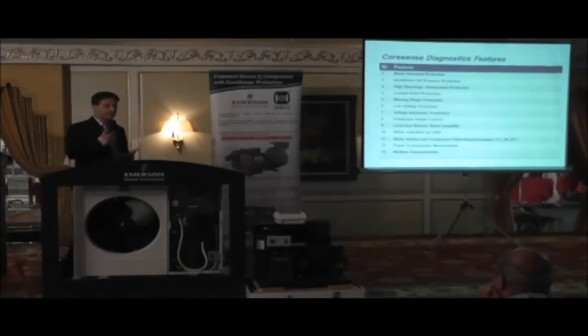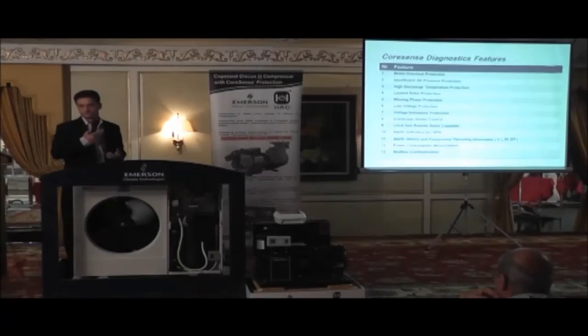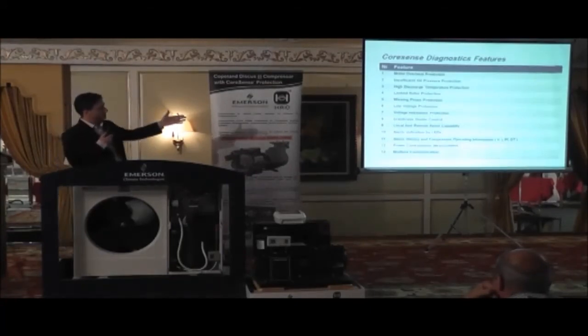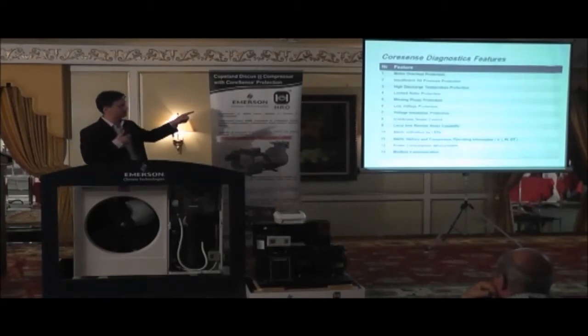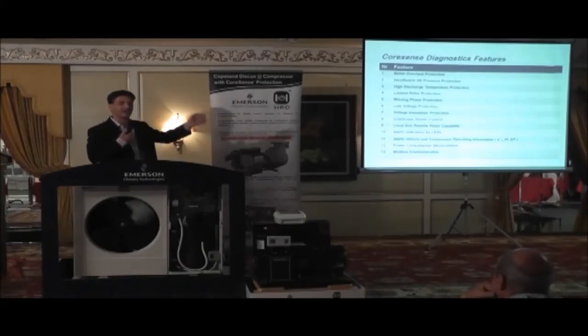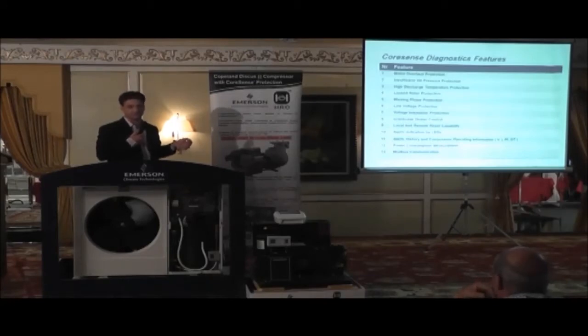Next, we are including a motor module, okay, which is an upgrade of the INT69. This will now include locked rotor protection, missing phase, low voltage, voltage imbalance. We're now able to do a complete protection of the motor. Depending on your supply, you would probably need to have added these accessories to your electrical board, phase failure or low voltage protection. This will now come standard with the Discus 3 compressor.